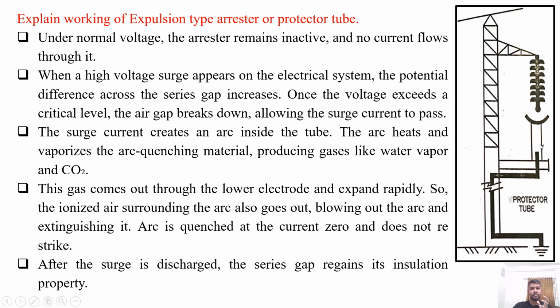The arc heats and vaporizes the quenching material, this inner wall of the protector tube, producing gases like water vapor and carbon dioxide. This gas comes out through the lower electrode and expands rapidly. So the ionized air surrounding the arc goes out like this, blowing out the arc and extinguishing it. The arc is quenched at the current zero interval and does not restrike, means the arc does not restrike again.